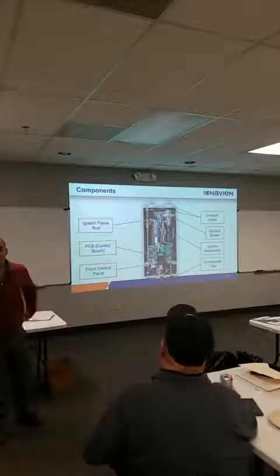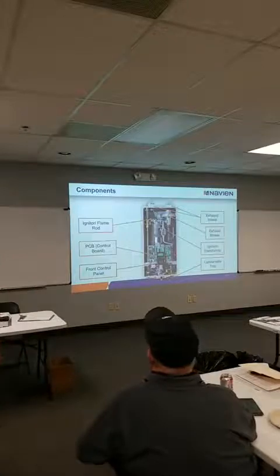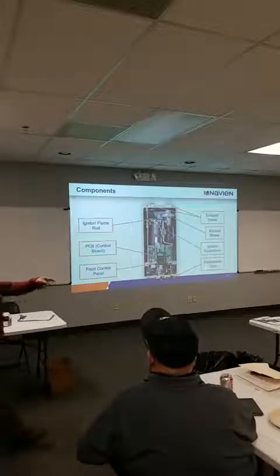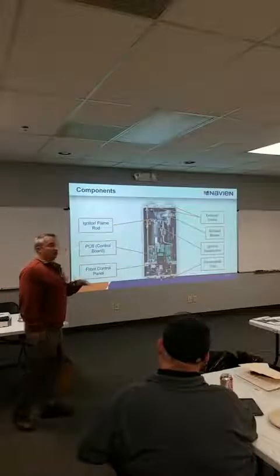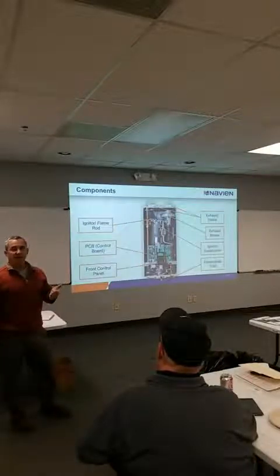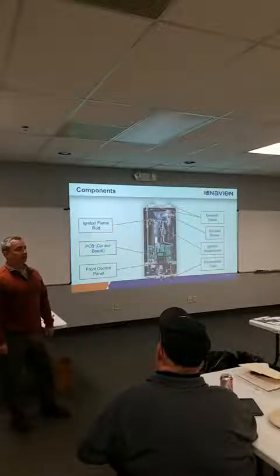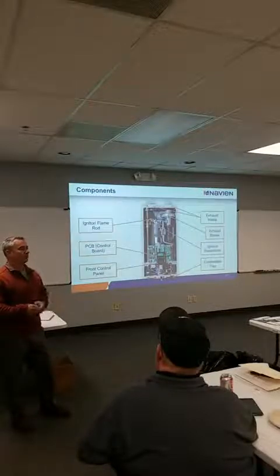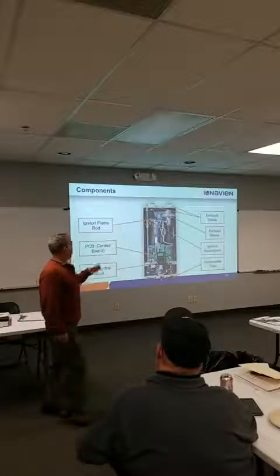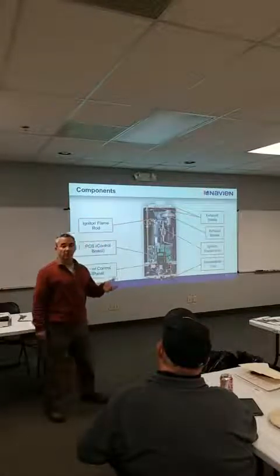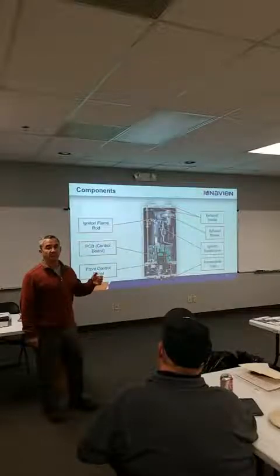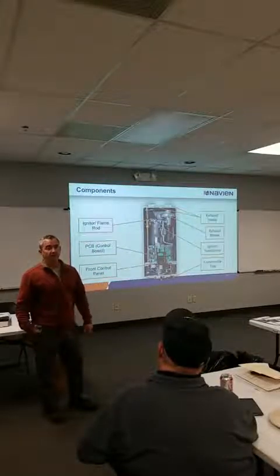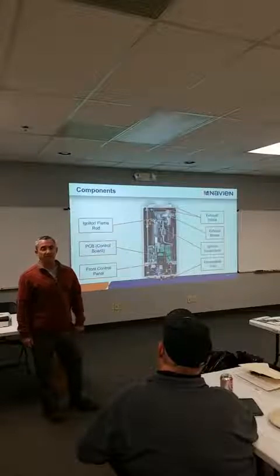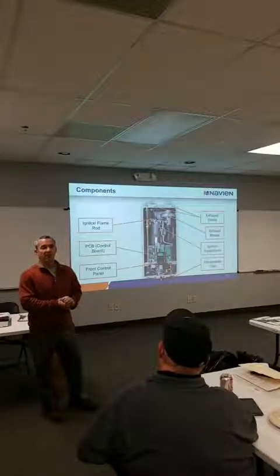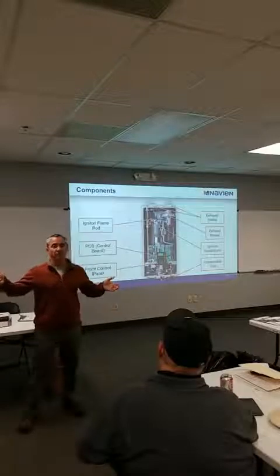How's the domestic output on the commercial? So the domestic, there's some charts and they're on all the literature. We lose a little on the domestic side as compared to our tankless water heater. The tankless water heater in our market at 120 will give you about 5.6 GPM. The best the combi is gonna do, that fire tube will give you about 5.4. The NCB combi will give you about 4.8. So we sacrifice going through that flat plate heat exchanger on the water tube combi.